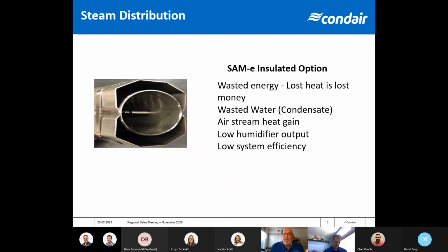It's a very, very efficient tube. Much more of the steam that we're spending a lot of money creating is going to go into the air as humidity instead of down the drain as condensate. So these are very, very good at what they do. And again, I think that these should be on every job. It's going to save the owner a lot of money in wasted water going to drain. So it's a really good way to go.